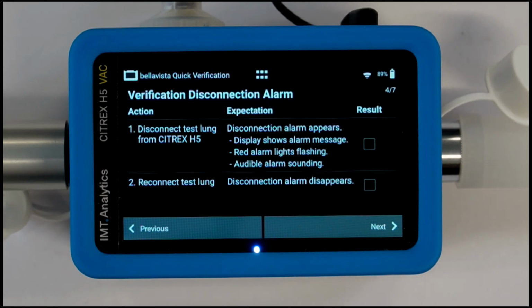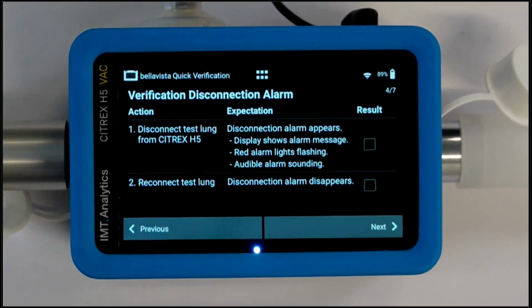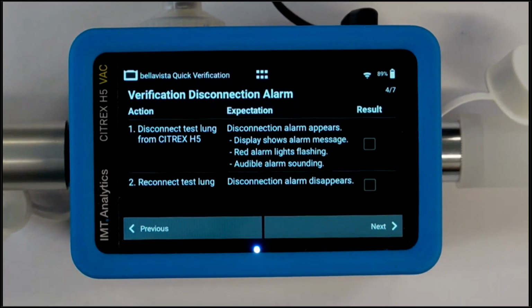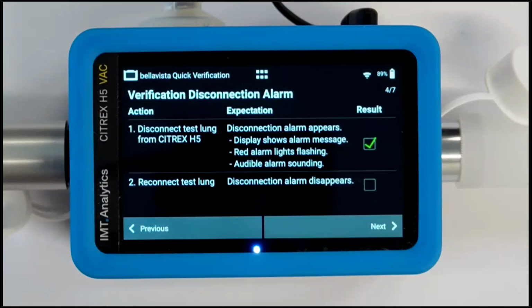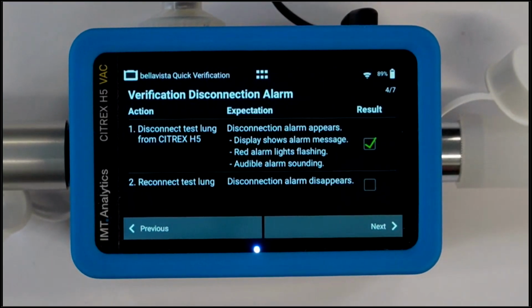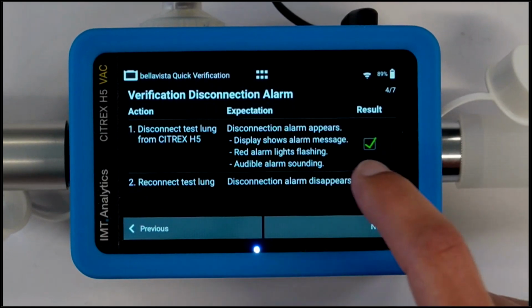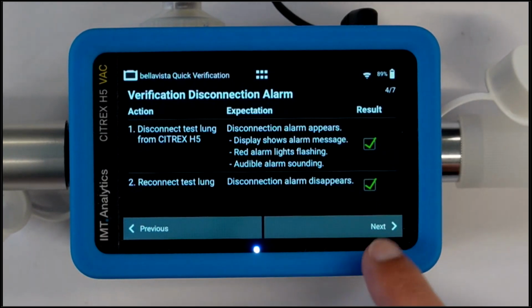So the next step in this Bella Vista Quick Verification app is that I have to disconnect the tubing from the device, and then the ventilator should trigger an alarm. And that's the case, as you can hear maybe in the background. So I confirm that. And then when I reconnect my circuit system, the ventilator should detect that as well, and the alarm should disappear. That happened here. So I confirm that as well.